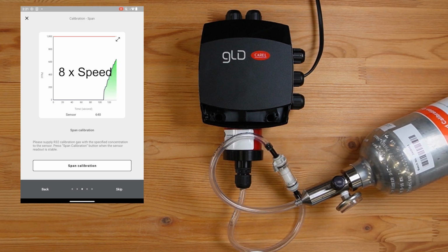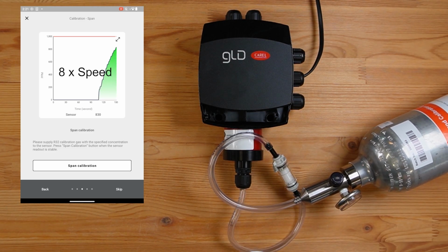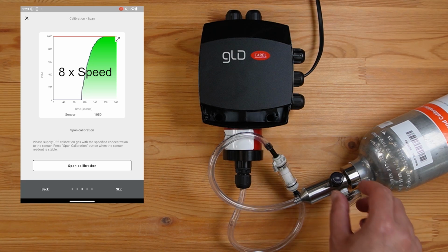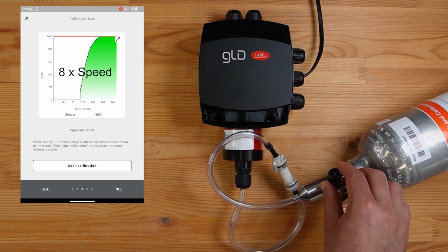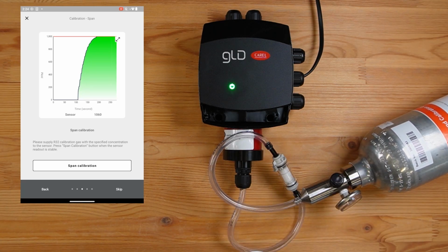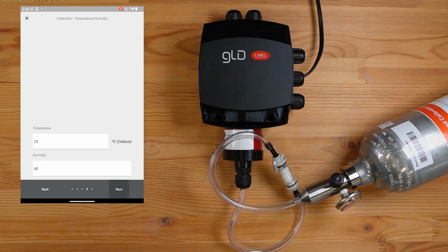Expose the sensor to the gas until it stabilizes at the preferred level. The sensor should be exposed to the known gas concentration for a limited time. The recommended time is 3 minutes, maximum 5 minutes. Click Span Calibration in the app to set the calibration concentration. Enter the room temperature and relative humidity.